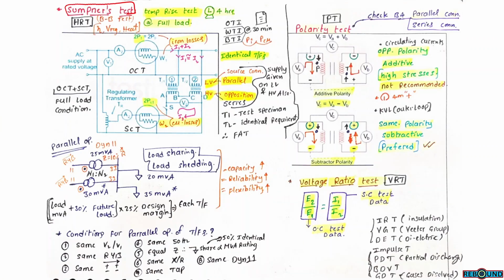Sumpner's test or back-to-back test. This is mainly used to find out the temperature rise in the transformer. This test has to be conducted for a minimum of 4 hours at full load.